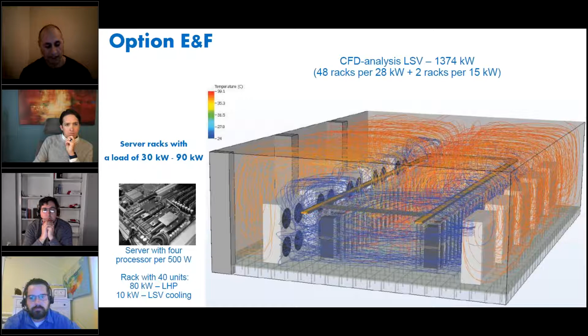So you can see the extremely low power consumption of LSV fans, and the use of innovative adiabatic coolers can increase the useful share of IT load up to 85%. So the point is that we can really decrease the energy consumption of our system per year, thanks to less and less energy consumption for the cooling systems.